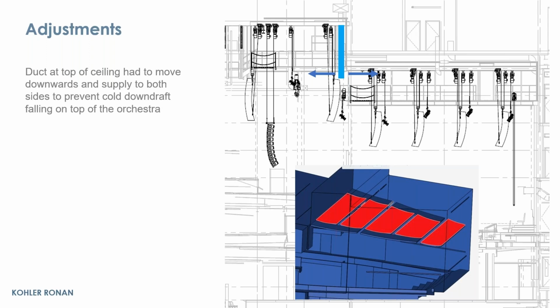Again, everybody's on the site together. It's really a team effort, because with every adjustment that they make, we have to make sure our airflow is balanced properly. So we have different sequences built into our program that change the supply air temperature and the supply airflow for the different acoustical configurations. So a lot of back and forth. I'm sure the engineers on the project would have a much more detailed answer, but from what I know, that's the story.